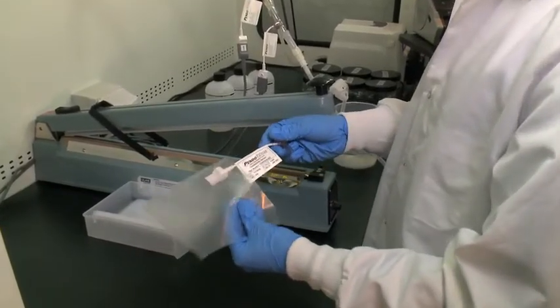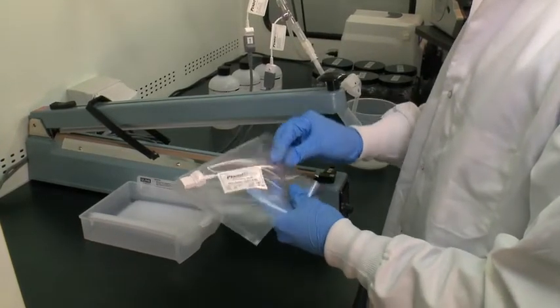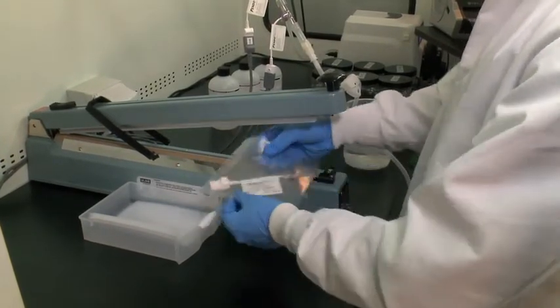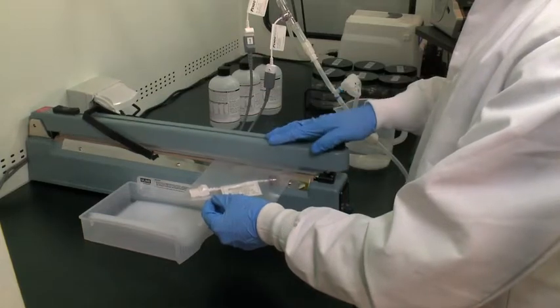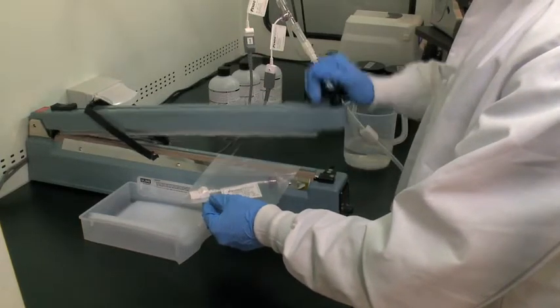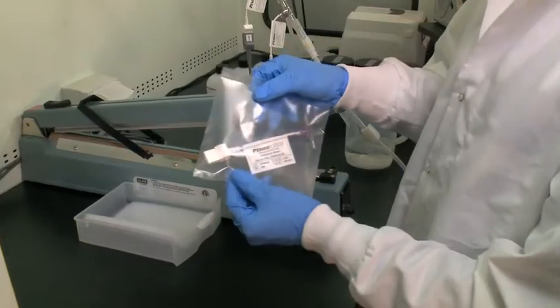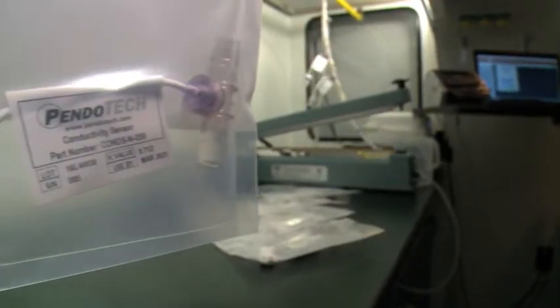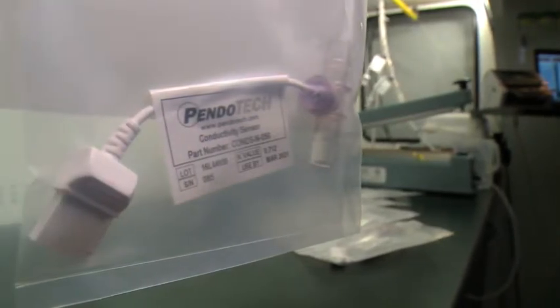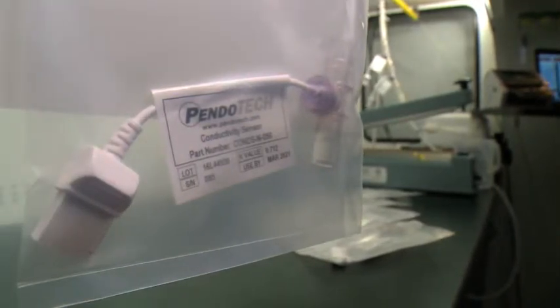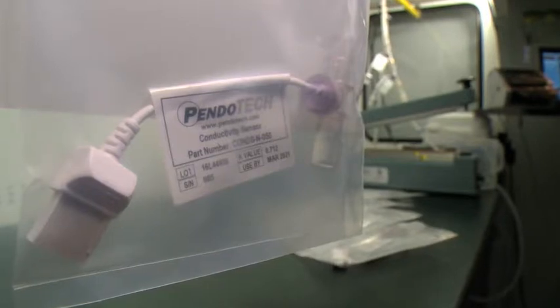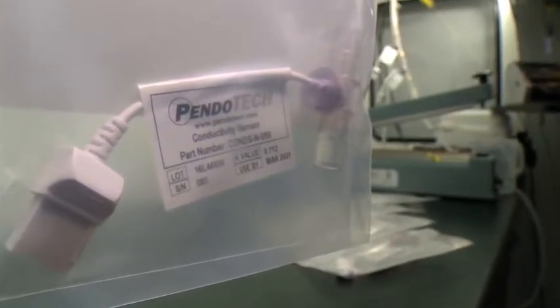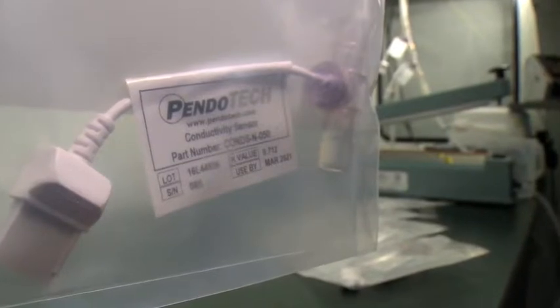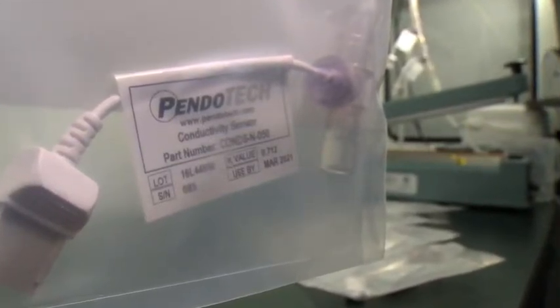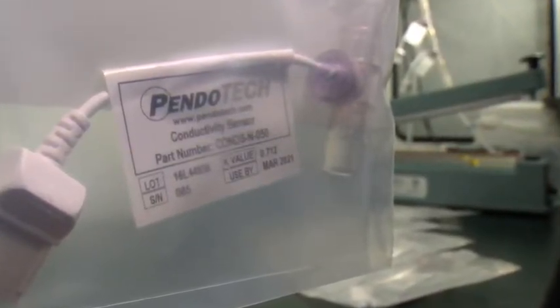The sensor is then sealed into a special barrier pouch to prevent moisture from entering during storage. No calibration is required because of the predetermined cell constant. The finished sensor performance with temperature correction is an accuracy of ±5% of reading to 50 mS/cm, and in the range of 50 to 100 mS/cm, typically ±5% of reading. And a 1-point calibration is optional to improve the accuracy on this upper range.